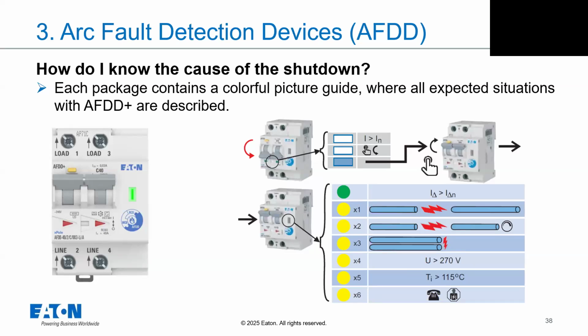Then it is good to look at the packaging of the AFDD, because each delivery with an AFDD comes with a user manual. This is a simple page of paper where you have all the important information available, and it is done in a way that you don't need to read any text. It is language neutral. Then you can see what happened: if you see the indication of this indicator, what was the reason, and so on.